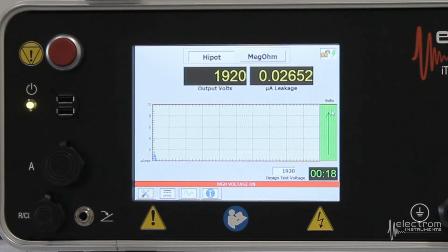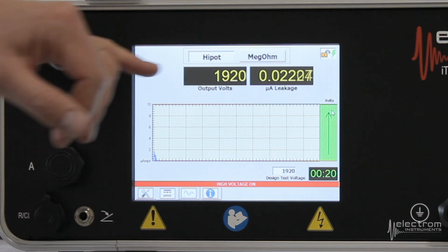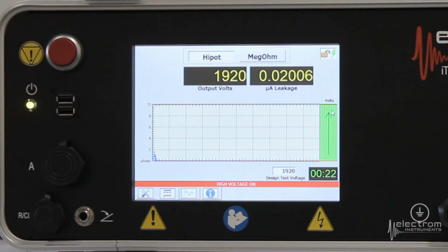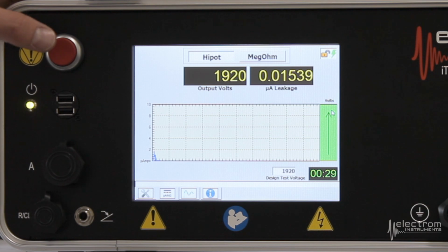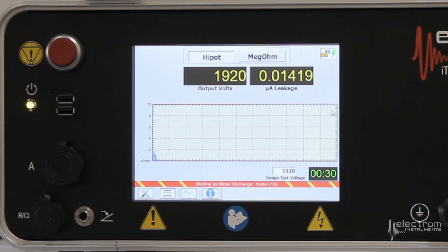So again, we can sit here for as long as we want to. Trick here is to keep an eye on the leakage current, make sure it's not accelerating or changing or bouncing around too much. This is pretty stable, so we are happy with this reading. Hit the red button, automatically discharges the windings again. All right, we're done with the Hipot test. We can move on to the surge test.